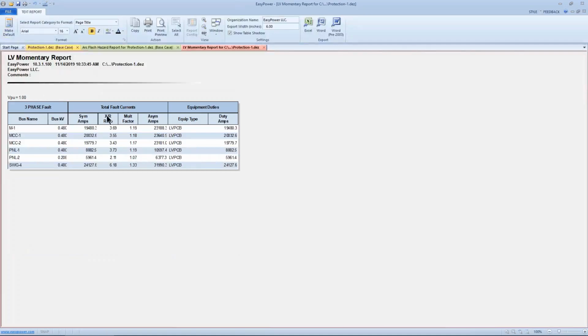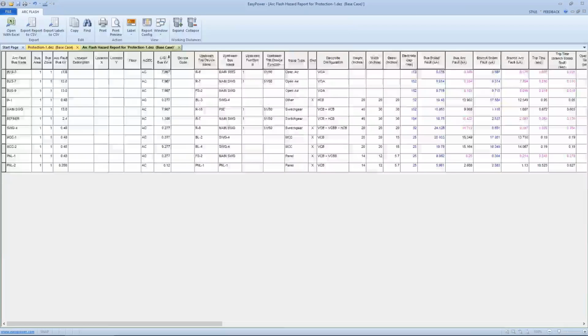And likewise on the low voltage momentary, the equipment duty amps, which have to be compared against the manufacturer's data sheet, are calculated based upon the type of standard. Now I didn't go into that. Let me do so.